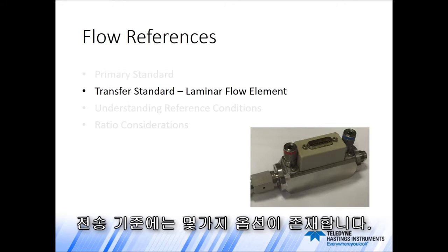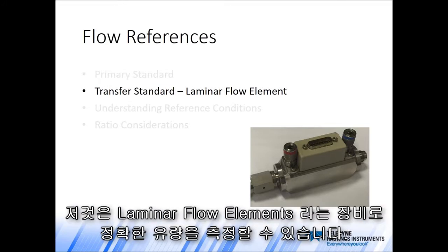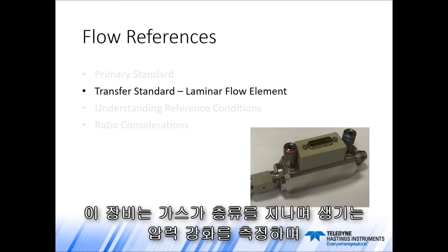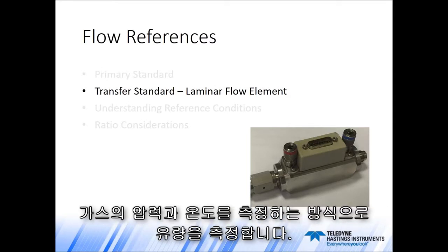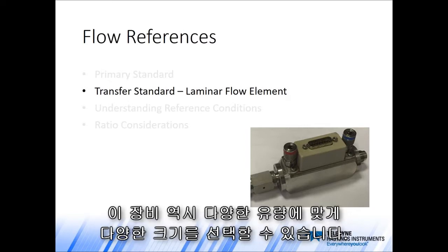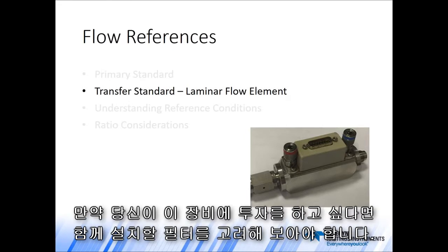There are some options for transfer standards. There are laminar flow elements that can offer very accurate flow measurements. And these devices measure the pressure drop across the laminar element, as well as the gas pressure and temperature, to determine the flow rate. Those also could be sized for different ranges of flow rates. So if you're going to invest in one of these, you want to consider a filter.